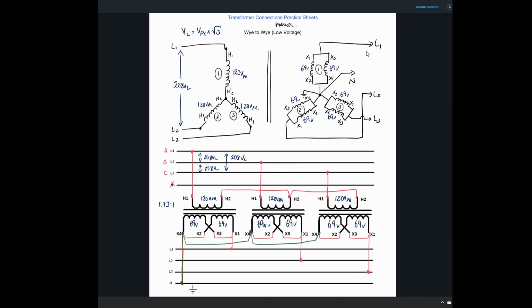So this one's funky as well, in that this voltage right here is 69 volts on the phase from any line to neutral, and this voltage right here is going to be 120 volts on the line. So for this transformer, or this configuration that we've created, we've got 208 volts 3-phase in, and then on the output, we're going to have 69 volts from line to neutral. That's our phase value. And then we've got 120 volts from line to line, and that's our line value.